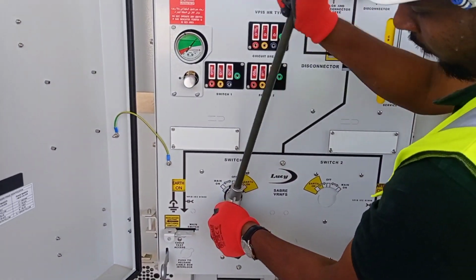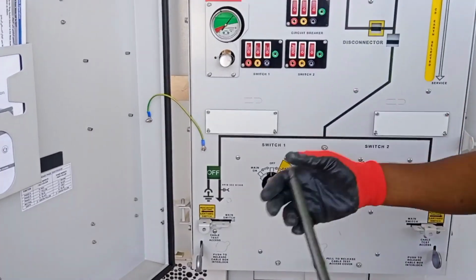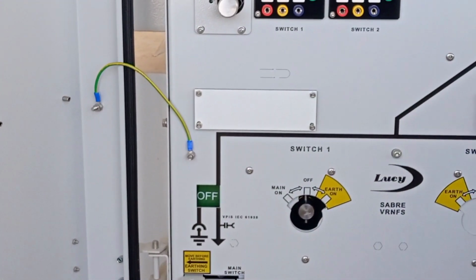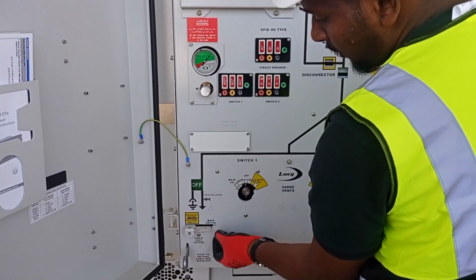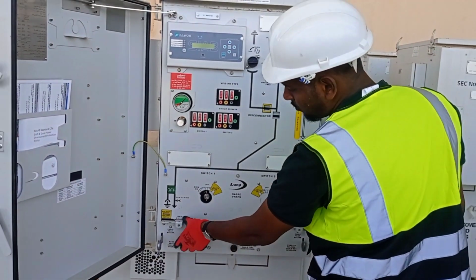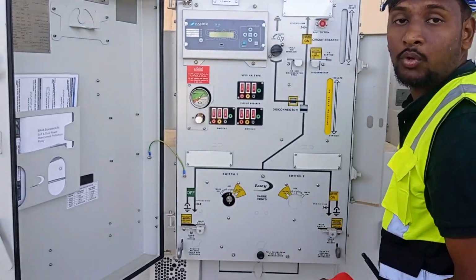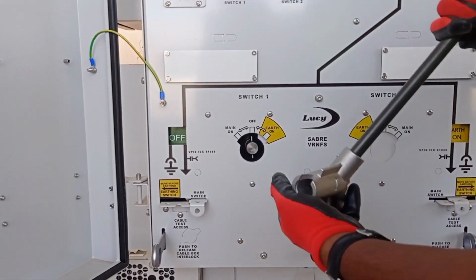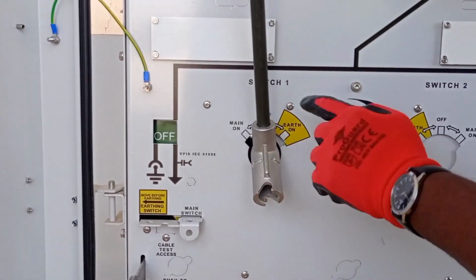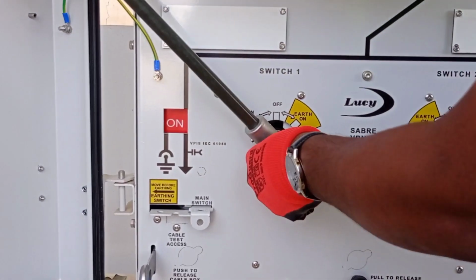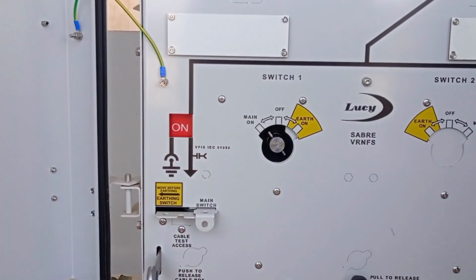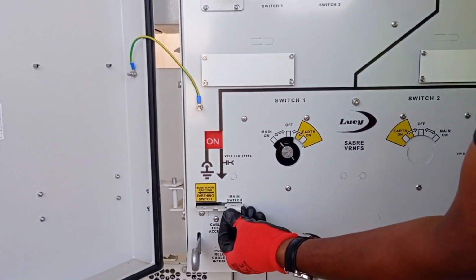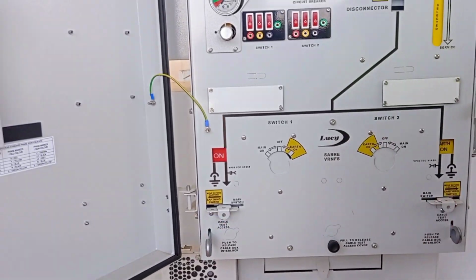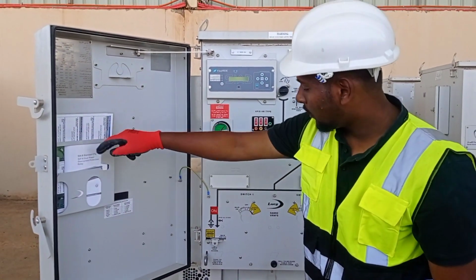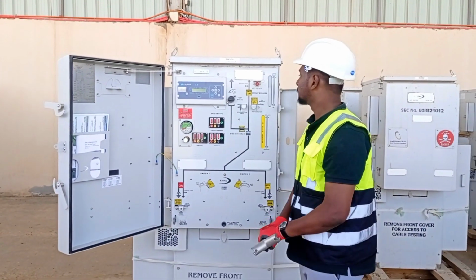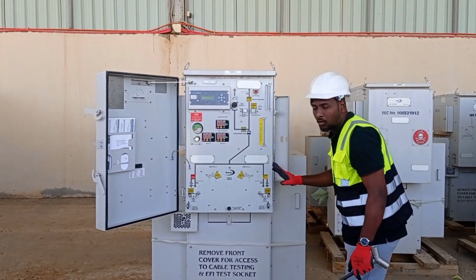Okay, now we can off. So now the earth position is off, and the earthing position completed. Now we have to put it on main switch, and now we are going to put the RMU on from off position to on. Okay, so we can use this handle, put offset and pull here, then it will be on. We can see. Okay, once we finish this one, we have to close this one and pull back this one. Okay, now the cable coming from this side is energized, and the same procedure is also same as here.